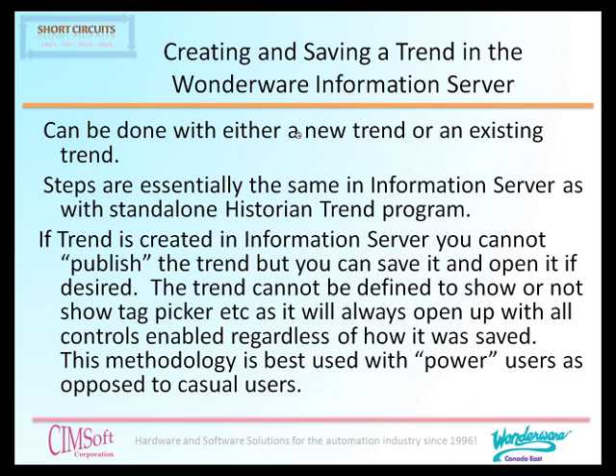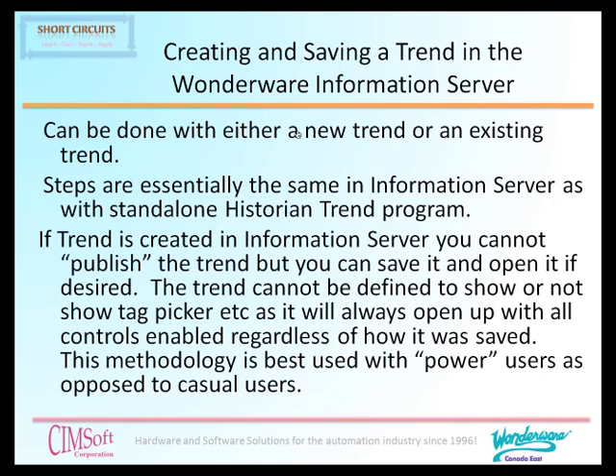However, the difference becomes that one is not able to actually publish a trend that is made in Information Server. You are able to save the trend and open it and look at it again. However, the major difference being that when a trend is made and saved in Information Server, you cannot put away some of the controls such as the tag picker. This can be a drawback to the more casual user as it may be somewhat intimidating, so therefore trends for casual users are probably best made and published using the Historian Client Trend tool.